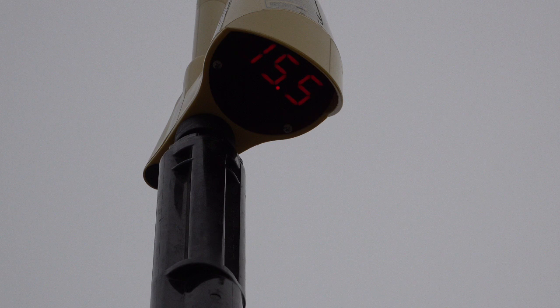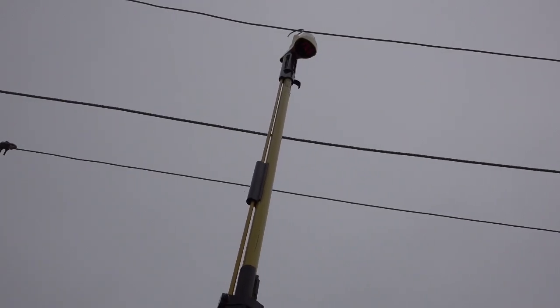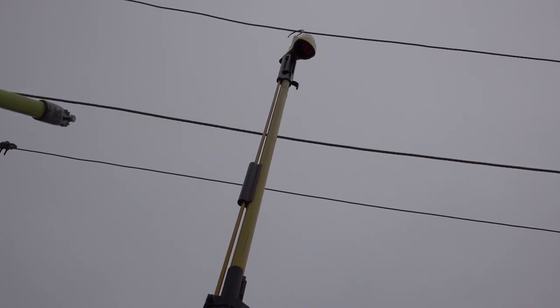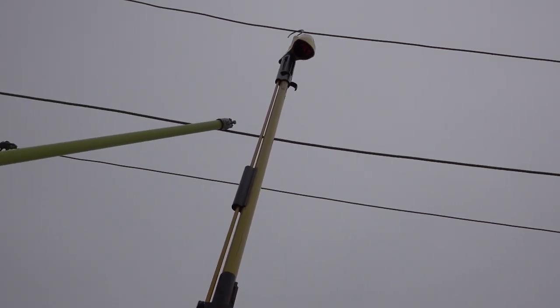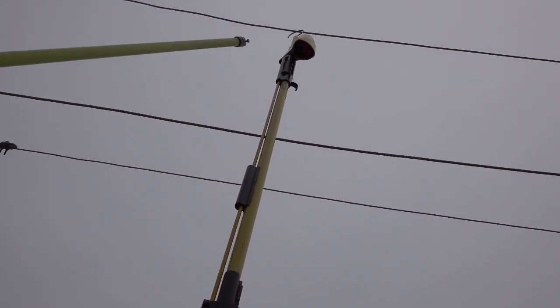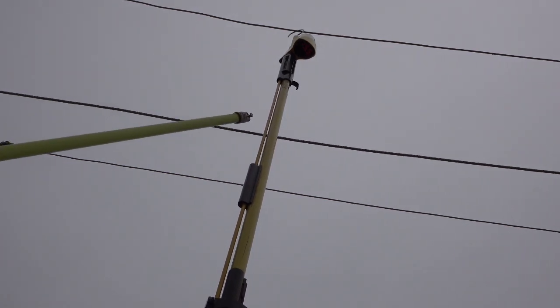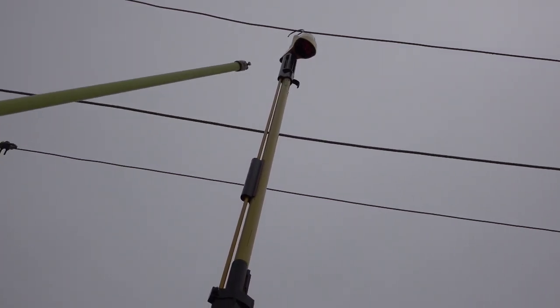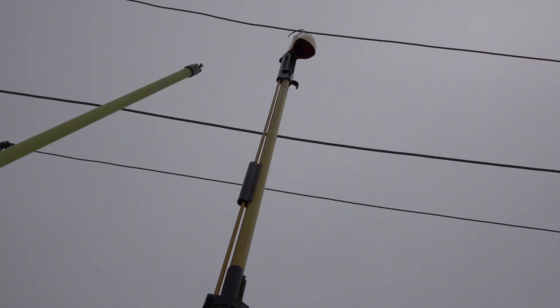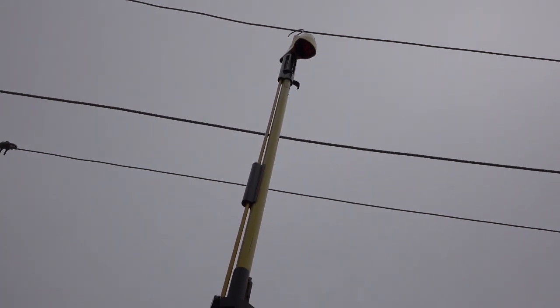As we created a bad situation in our URD example by inserting the meter close to a ground plane in the upper left bushing, we have now created a similar example in an overhead application. Notice on the center phase, the meter probe is right above the neutral wire. The neutral wire is a ground plane, so now it can capacitively couple to the neutral wire, which causes the reading to be higher than the outside phase.